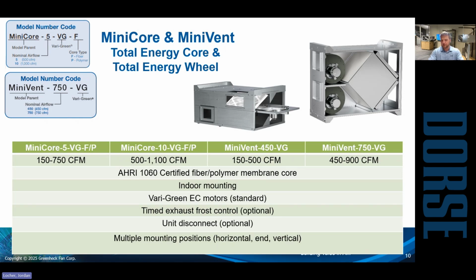I will mention too, that mini core that's pictured on the right there, that unit can also be reoriented in any direction, so horizontal and vertical. And then they do have configurable ductwork as well, so it is field configurable. Basically, we ship them as is from the factory, and then they have blank off plates. You can see on this mini vent here, there are 2 different openings. One will have a cover plate on it, one will not, and you can change that ductwork accordingly. So very, very flexible unit.